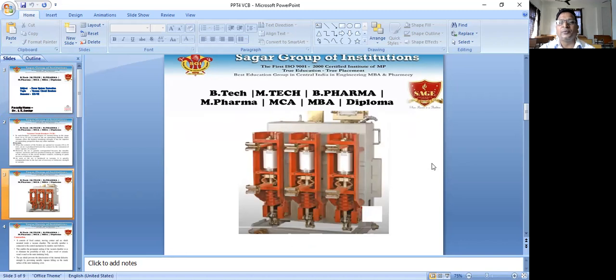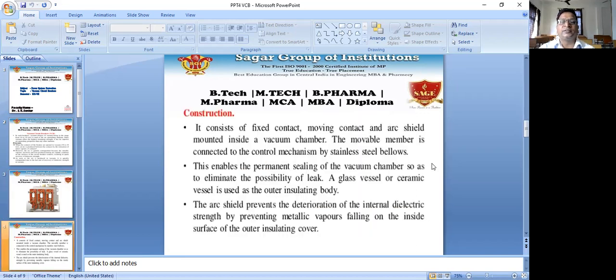So here is the diagram of the VCB, vacuum circuit breaker. Construction: it consists of the fixed contact, moving contact, and arc shield mounted inside a vacuum chamber. The movable member is connected to the control mechanism by stainless steel bellows. This enables permanent sealing of the vacuum chamber so as to eliminate the possibility of leaks. A glass vessel or ceramic vessel is used as the outer insulating body. The arc shield prevents the deterioration of the internal dielectric strength by preventing metallic vapor from falling on the inside surface of the outer insulating cover.